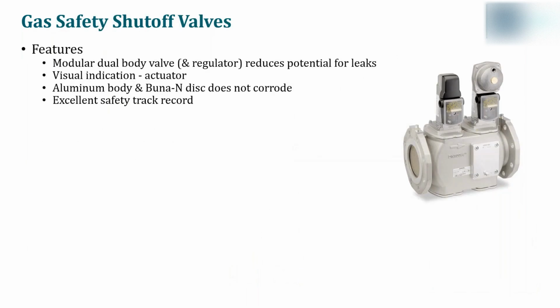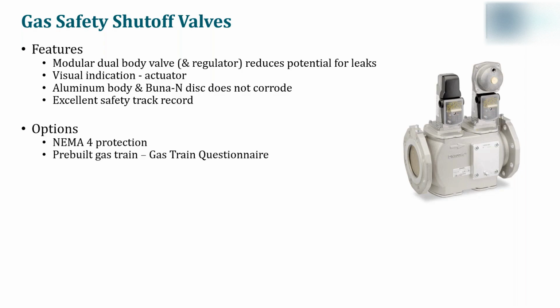Now, some of the features of the gas safety shutoff valves: it is a modular dual body valve and regulator, which reduces the potential for leaks. It offers you a visual indication on the actuator to see that your valve is open or closed and where it's positioned. It is an aluminum body and Buna N disc that does not corrode. And finally, the valve has an excellent safety track record. Options include NEMA 4 protection, and you also have the option for a pre-built gas train. Finally, sizing. You have the SSOV sizing program. We will cover the pre-built gas train SSOV sizing program in a bit, but first we're going to cover what the advantages of the Siemens gas train design are.